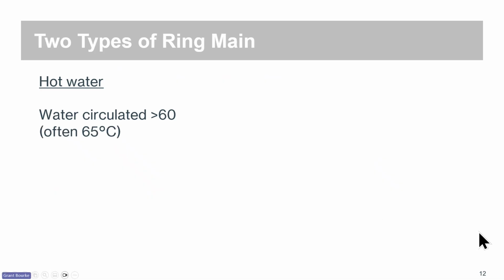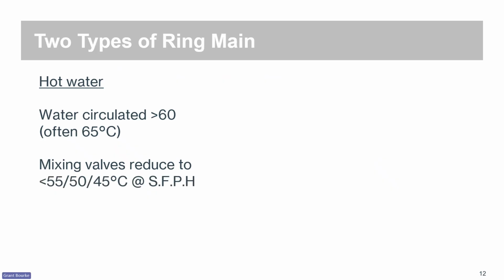So we've got two fundamental types of ring main. We've got one for hot water. We'll see if my voice lasts this webinar. So we're going to circulate the water at greater than 60 degrees, send it off from the hot water plant at more than 60, often 65 degrees. We're going to use mixing valves at the branch offtakes or close to the fixtures to reduce the hot water at the sanitary fixtures to the applied or the acceptable temperature.